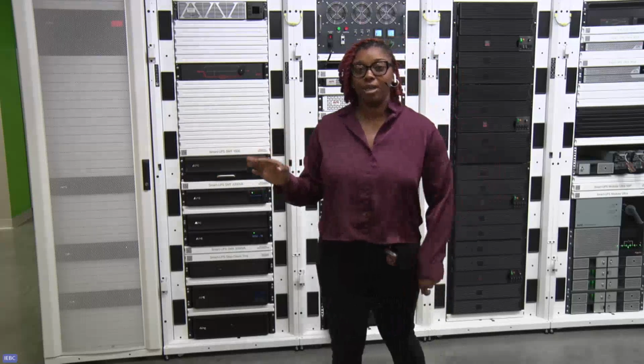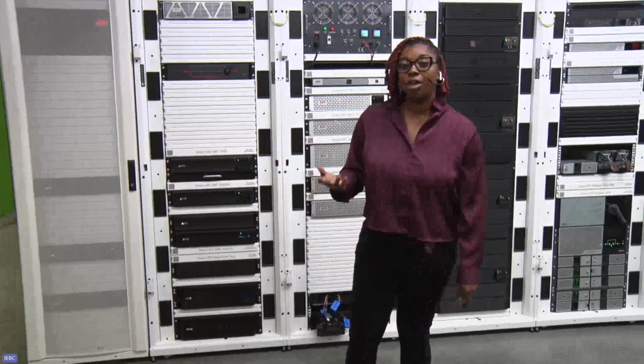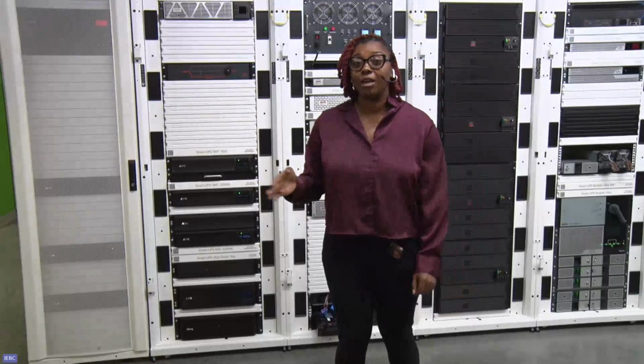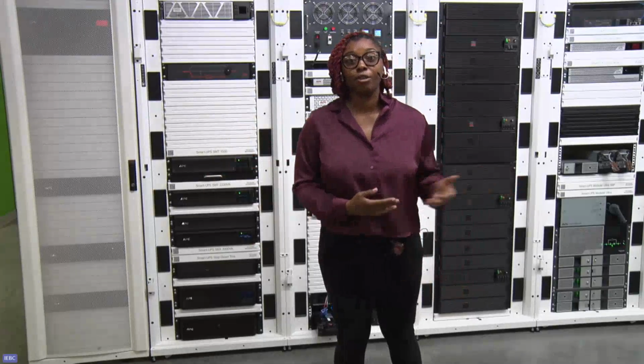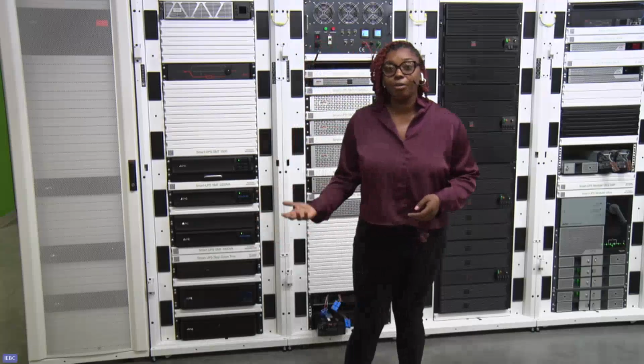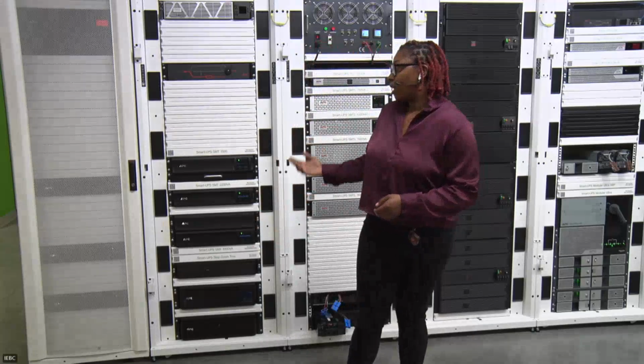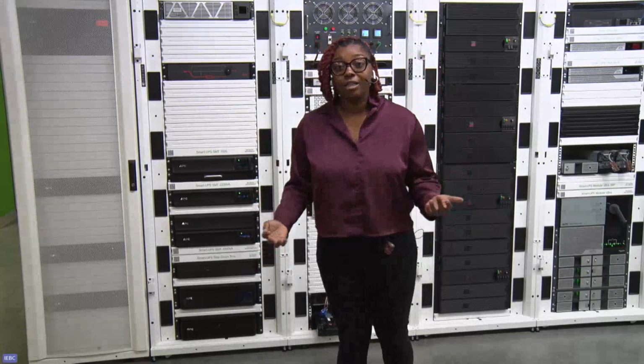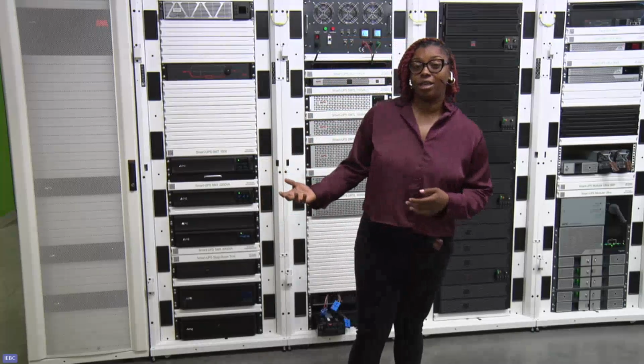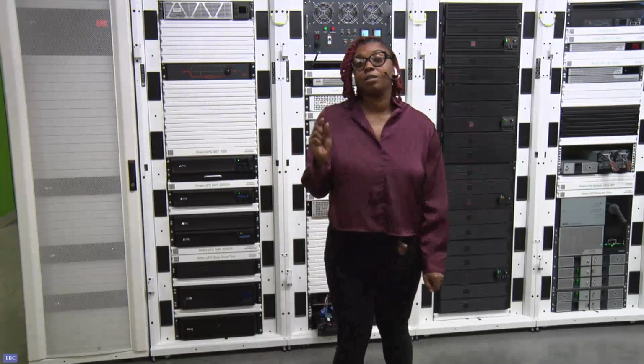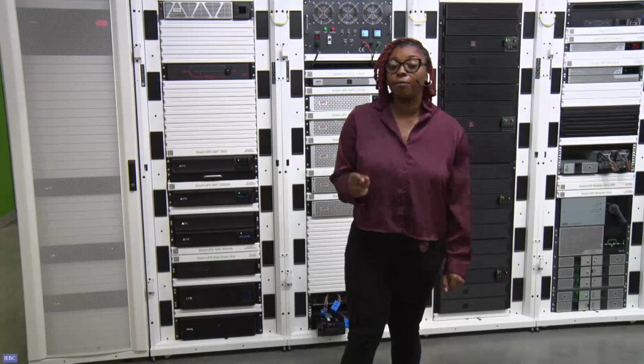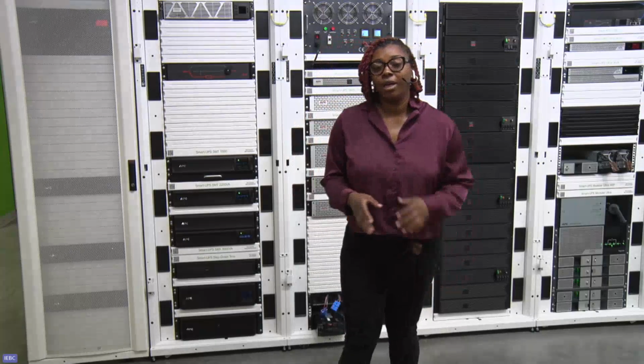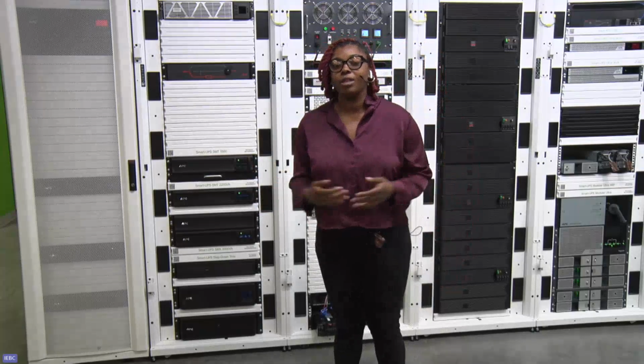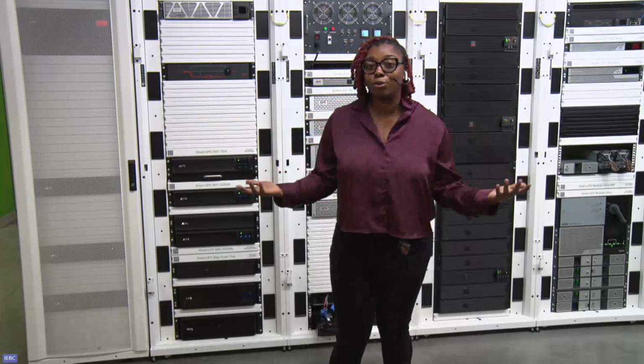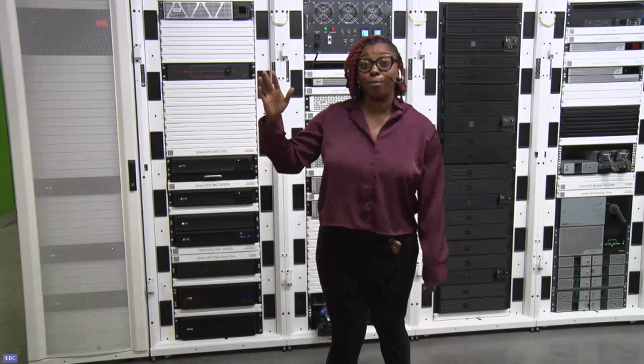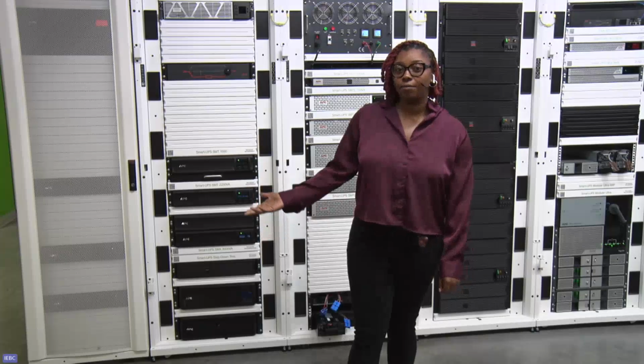If you have spikes and sags in your power, your line interactive UPS system will clean that up so you get good power to your equipment. If it has to go to battery, that means there's a complete outage, and now battery is carrying your load. There's a very small drop in power, only a few milliseconds, but there is a drop. It compares to being in your house during a storm when you lose some power and your lights dim a bit.